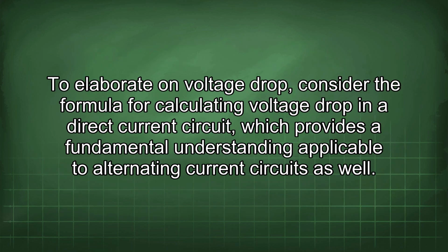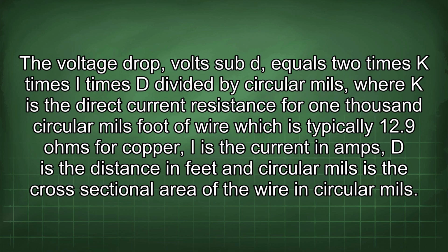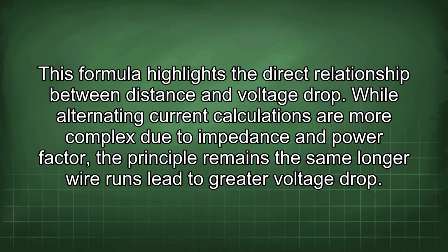To elaborate on voltage drop, consider the formula for calculating voltage drop in a direct current circuit, which provides a fundamental understanding applicable to alternating current circuits as well. The voltage drop, V sub D, equals 2 times K times I times D divided by circular mils, where K is the direct current resistance for 1000 circular mils foot of wire, which is typically 12.9 ohms for copper. I is the current in amps, D is the distance in feet, and circular mils is the cross-sectional area of the wire in circular mils. This formula highlights the direct relationship between distance and voltage drop. While alternating current calculations are more complex due to impedance and power factor, the principle remains the same. Longer wire runs lead to greater voltage drop.